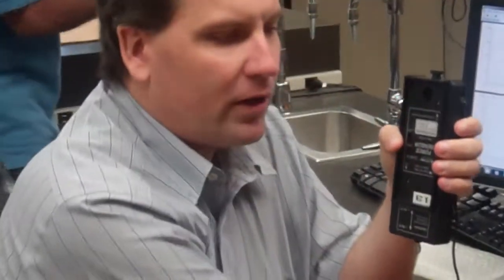Okay. So calibrating the force probe. The way you calibrate any of these things is you put a known force on them. Now, where are we going to get a force that doesn't change? It's always constant. I know. Let's use gravity. What we have here is a 1 kilogram weight. Its mass is 1 kilogram. So what is its weight? Weight is a force. It's going to be equal to the mass times gravity. So we have 1 kilogram times gravity, which is 9.8. So this has a weight of 9.8 newtons, which is a force. I know sometimes we mix up mass and weight, but in terms of the force, this one here has a force of 9.8 newtons down. All the time. Not just on Fridays, by the way.